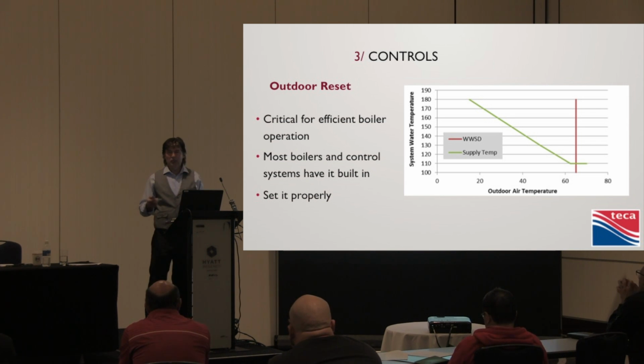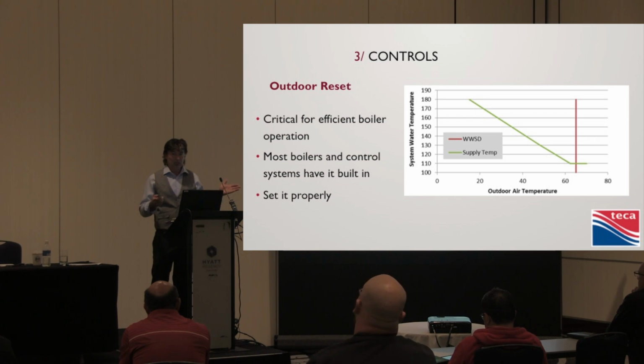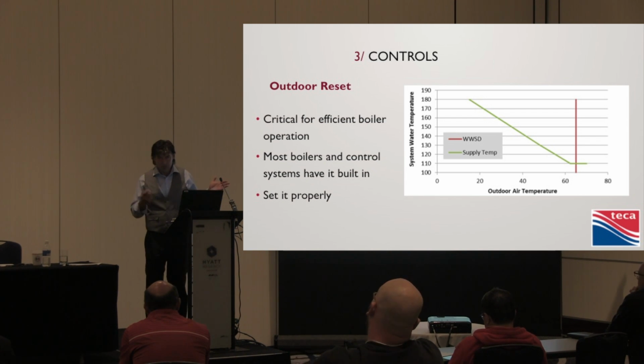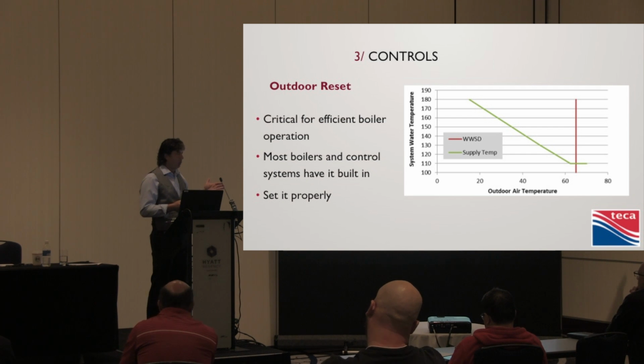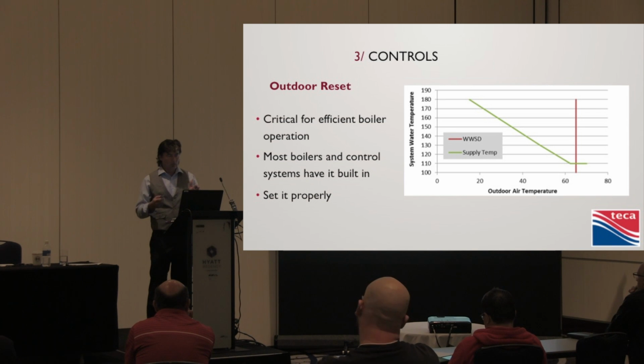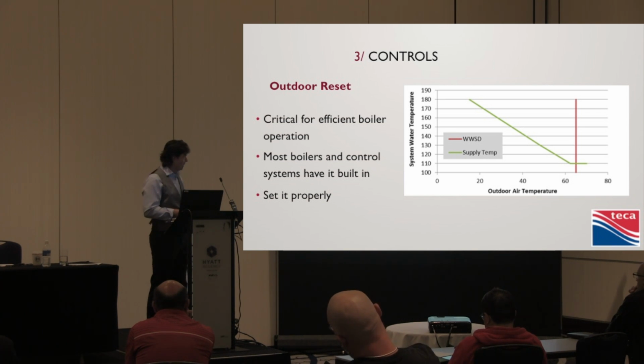So today, maybe it gets chilly tonight or whatever, your radiant heating comes on. Our design, once again, was for 130 degrees F in the floors. But do we really need 130 tonight to heat our house? I don't think so, or let's say September 30. We could probably use about 79 degree water. You run 79 degree water through that boiler, it's condensing like crazy. You run it through that heat pump, whether it's geothermal or air source, it's really operating efficiently. So we have to tell the boiler what to do.